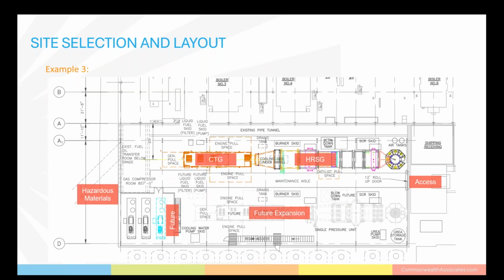Example 3 is an existing utility whose original building wall ended at column row A. Our addition extended the new plant wall down to column row D. The plant already had most of the services needed to operate a CHP, so the separate areas are limited to the CHP itself. As you can see in this design, we also left space for a future additional smaller unit, as well as additional space for future lube oil equipment.